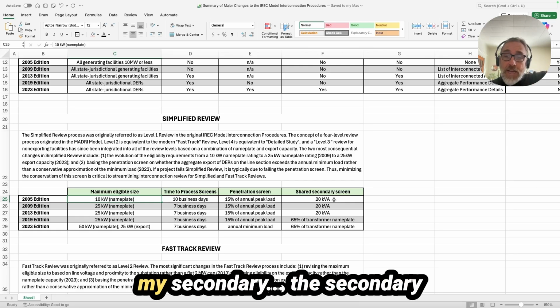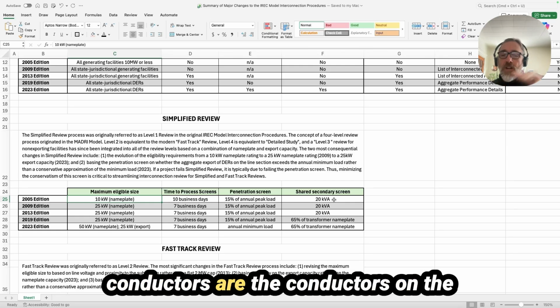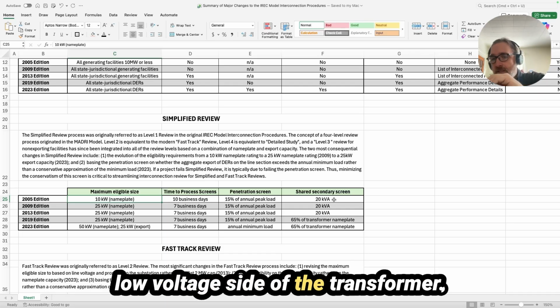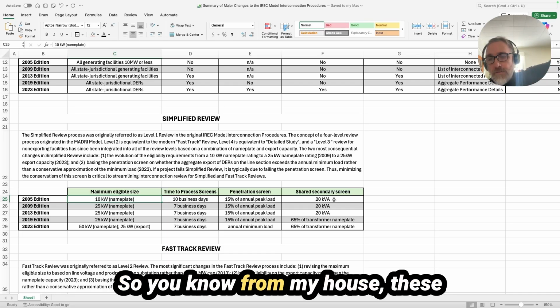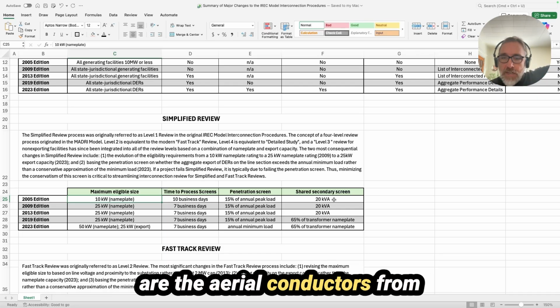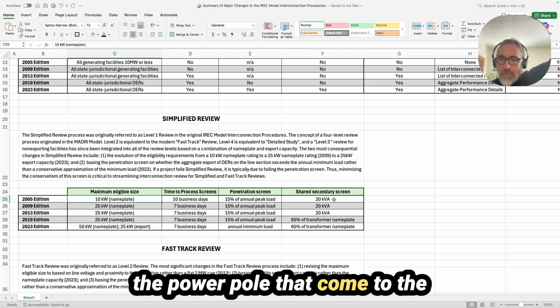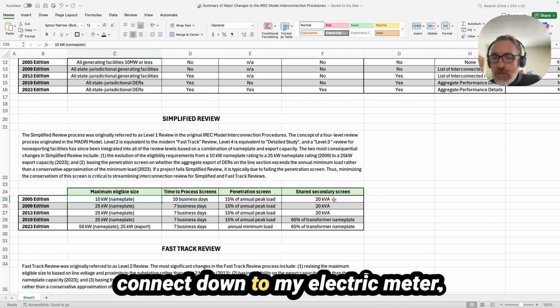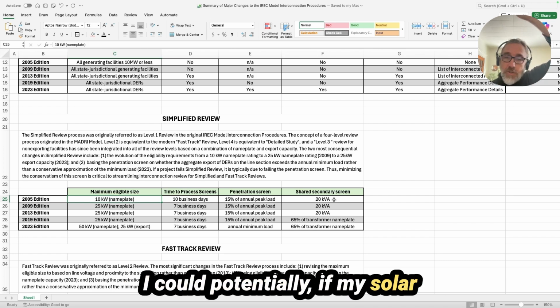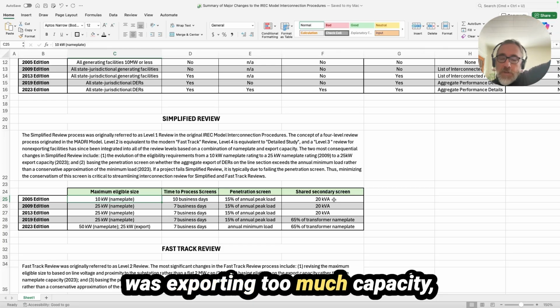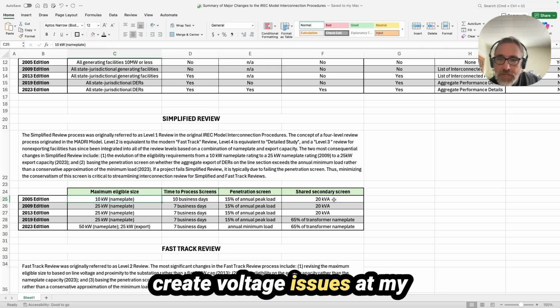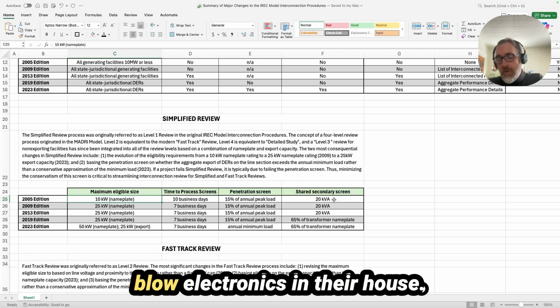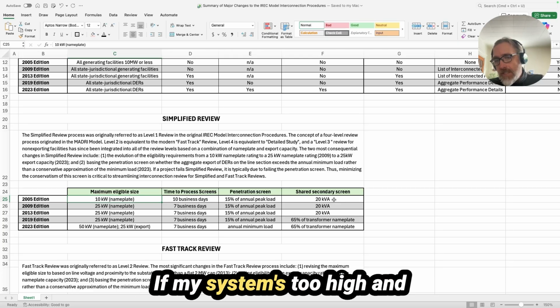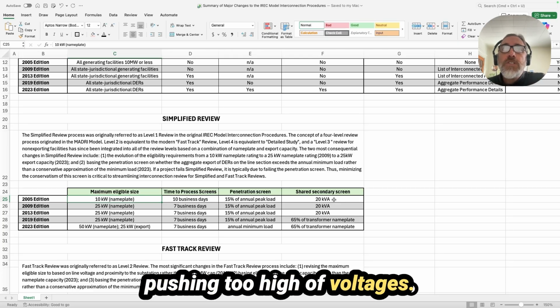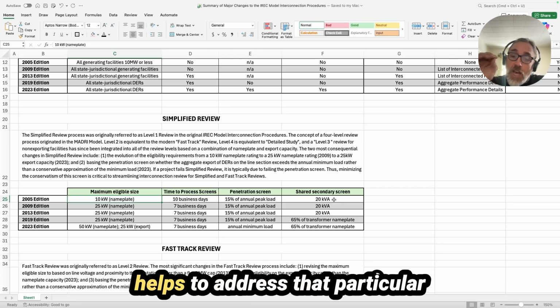that high voltage that I create on my secondary, the secondary conductors are the conductors on the low voltage side of the transformer. So, for my house, these are the aerial conductors from the power pole that come to the weatherhead on my house and then connect down to my electric meter. I could potentially, if my solar was exporting too much capacity, create voltage issues at my neighbor's house and potentially blow electronics in their house if my system's too high and pushing too high of voltages. The shared secondary screen helps to address that particular issue.